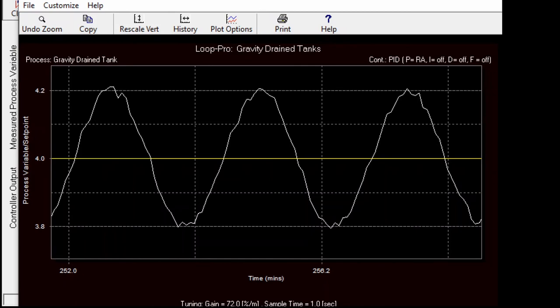So we got the ultimate gain to be 72 and the ultimate period to be something in the range of around 2.4 minutes. Then using the Ziegler-Nichols tuning rules, we can find out what will be the parameters for the controllers. Meaning if you choose a PI or PID controller, we can set the controller parameter according to those tuning rules.